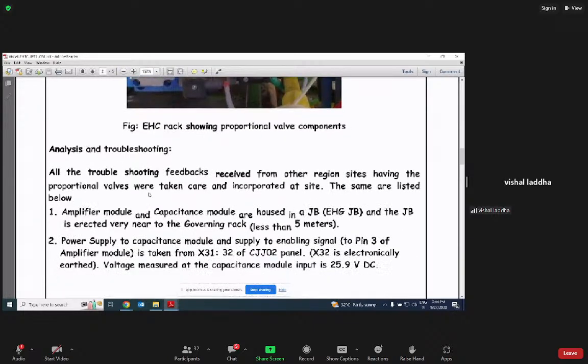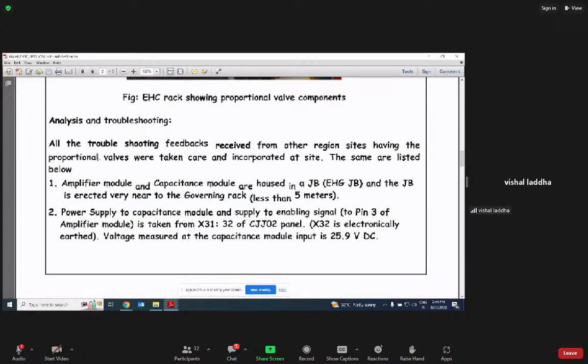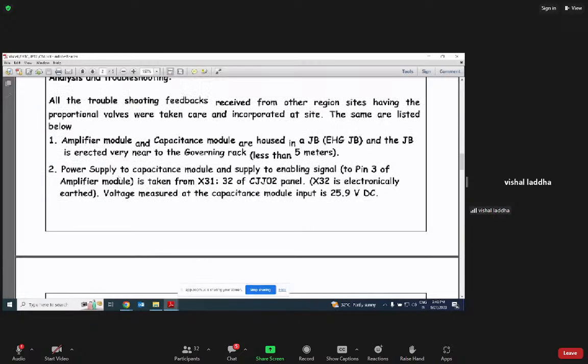So in analysis and troubleshooting, all the troubleshooting feedback received from the other regional sites having the proportional valve was taken care of and incorporated at site. The same are listed below. The amplifier module and capacitance module are housed in a JB, and the JB is erected very near to the governing rack, less than 5 meters. Before, it was away from the amplifier module. Power supply to the capacitance module and supply to the enabling signal is also taken care of, and it is electronically earthed.